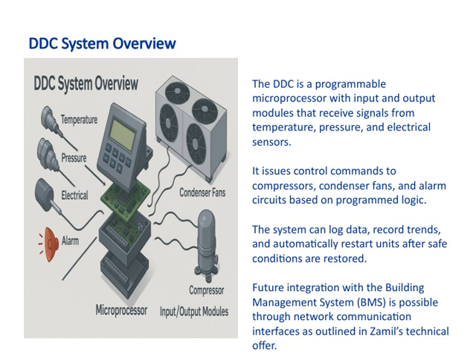The key here is that all these actions are driven by programmed logic, allowing for precise and automated control. Another important feature is that the system can log data and record trends over time. This helps us analyze performance and make informed decisions. It also has the capability to automatically restart units once safe conditions are restored, ensuring continuous operation without manual intervention.